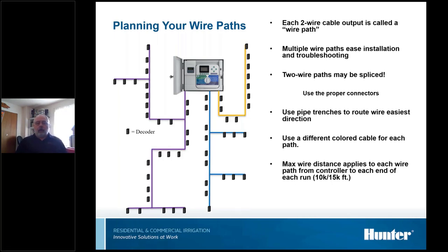Distances vary a little bit, but on an ACC controller, using the standard 14-gauge wire that we call ID1, we can go 10,000 feet, measured from the furthest decoder back to the controller. That does not include all the branches. That's a long way. If we use the 12-gauge wire, ID2, we can go 15,000 feet, or 3 miles.